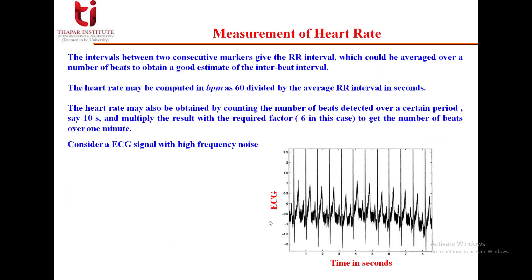To measure heart rate using this algorithm: the intervals between two consecutive detected QRS markers give the RR interval, which can be averaged over a number of beats to obtain a good estimate of the inter-beat interval. Heart rate in beats per minute is computed as 60 divided by the average RR interval in seconds. Alternatively, count the number of beats detected over 10 seconds and multiply by 6 to get beats per minute.